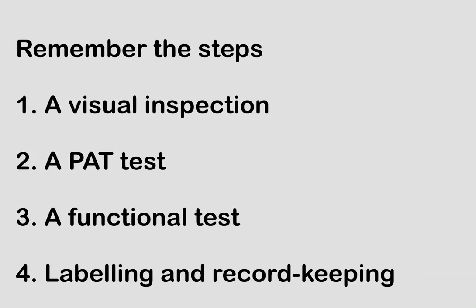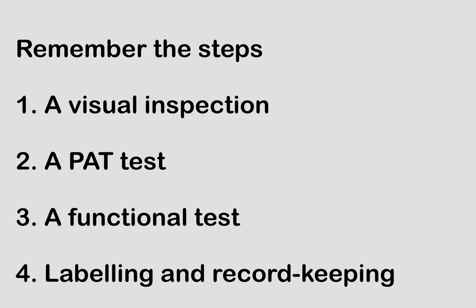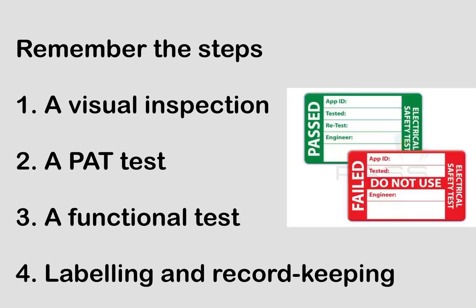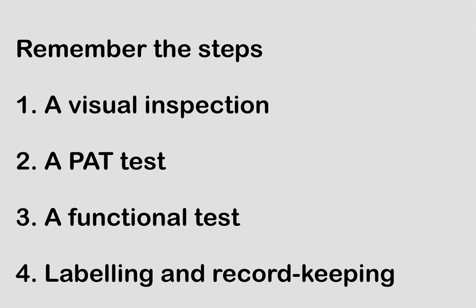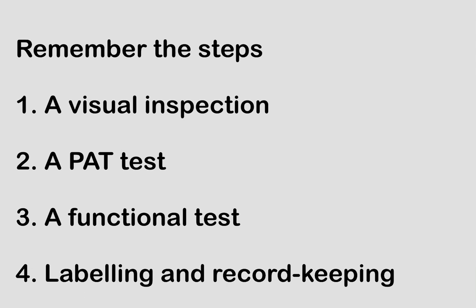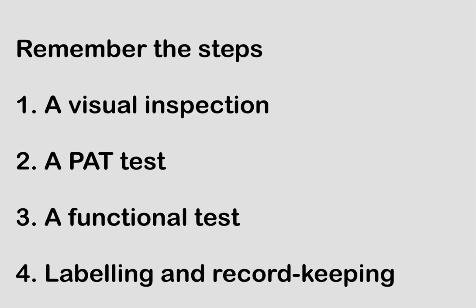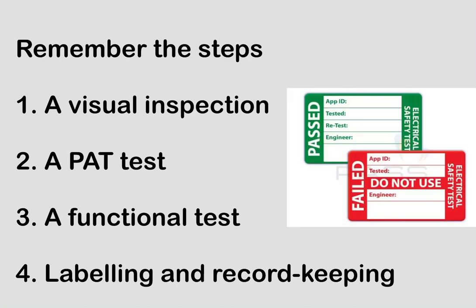Before proceeding to the PAT test you should remember four things. First is visual inspection — it is very important to check your equipment visually. Second is the PAT test itself, for which there are five methods to conduct. Third is a functional test — it is very important to check if your asset or equipment is functioning. Fourth is labeling and record keeping. Once you have done the test, you put a pass or fail sticker on the asset. If it fails, you cannot use it and must keep it out of service.